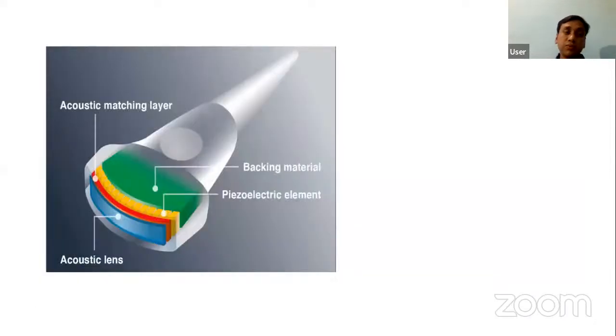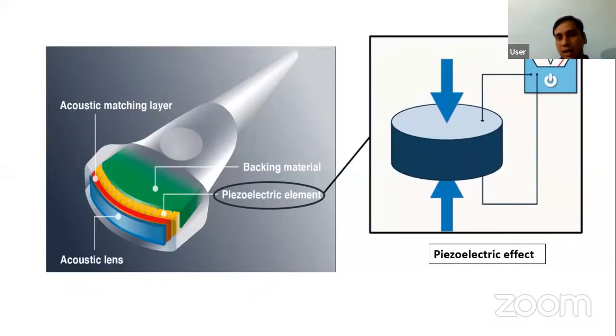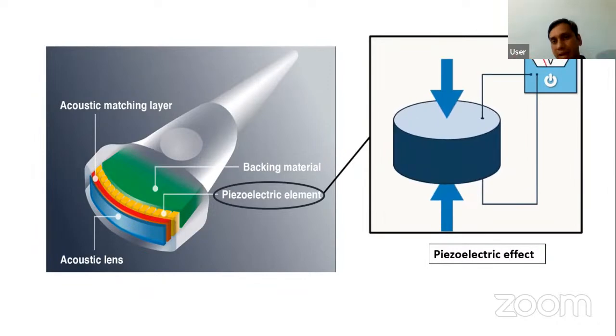But the question is how this probe is actually creating an ultrasound wave. For that, we have to open up the probe to see what structure is actually creating this ultrasound wave. When you open up, there are so many structures, but the structure which is important to us is the piezoelectric element, which has a very specialized property called the piezoelectric property. It states that when mechanical stress is applied to this special type of element, it creates electric charge. And in reverse, if you apply electric charge to this object, there will be mechanical deformation of this element, and it will vibrate and create sound waves. So this type of material is used in our probe so that our probe both receives a sound wave and also creates a sound wave.